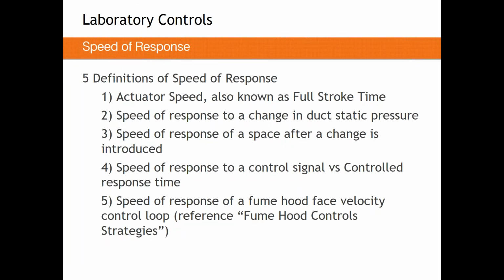The first and most simple way is actuator speed, or full stroke time. So if you take a Belimo actuator and look at its cut sheet, it will tell you the full stroke time. So from minimum to maximum, how long does it take this actuator to move? A standard speed Belimo takes about 90 seconds. A high speed Belimo takes 4 seconds or less. Simple fact. Now, this doesn't tell you the whole picture. It tells you actually a very small part of the picture.